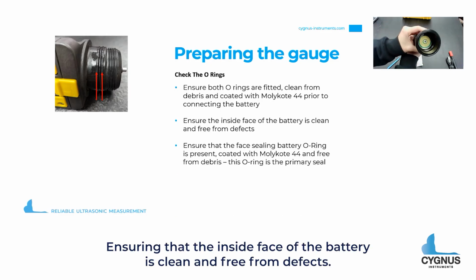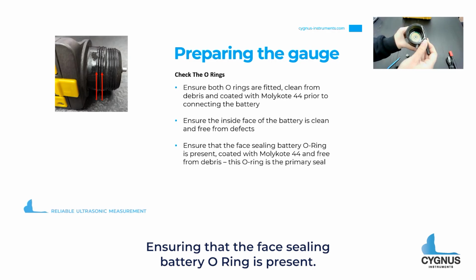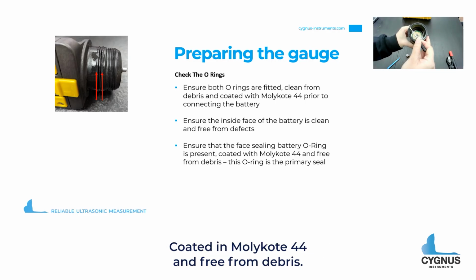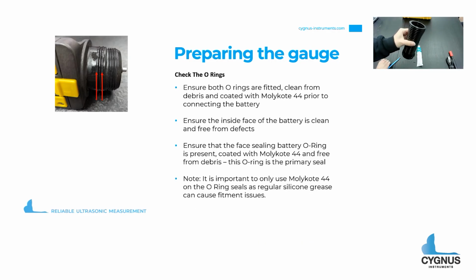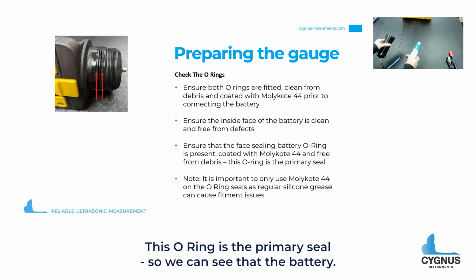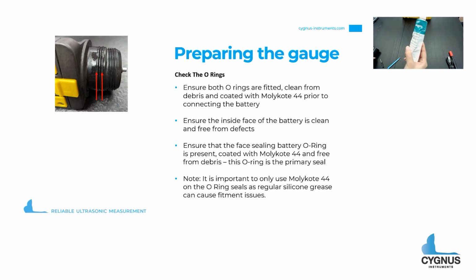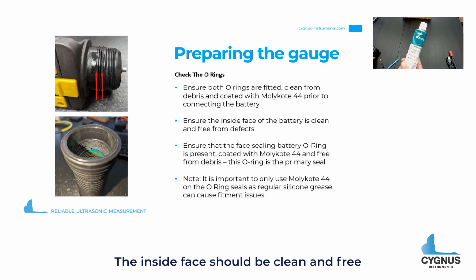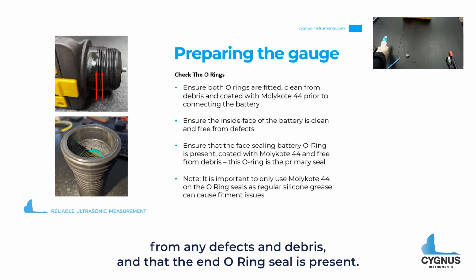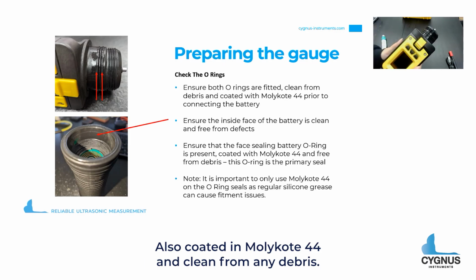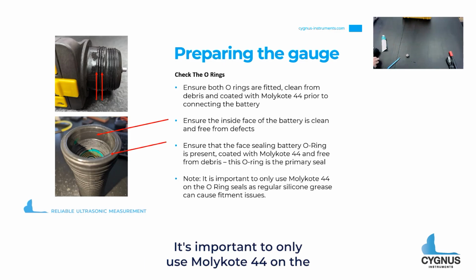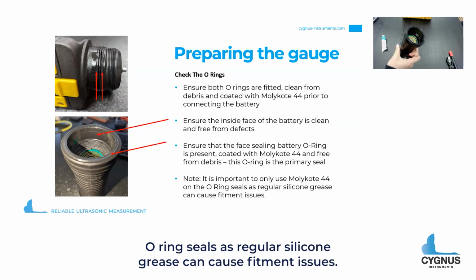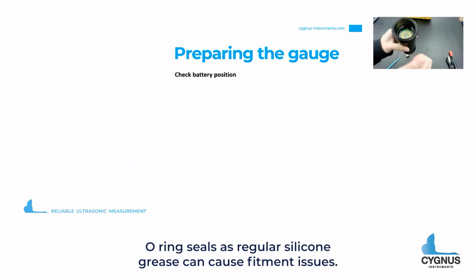Ensure that the inside face of the battery is clean and free from defects. Ensure that the face sealing battery O-ring is present, coated with Molykote 44 and free from debris. This O-ring is the primary seal. So we can see there the battery, the inside face should be clean and free from any defects and debris, and that end O-ring seal is present, also coated with Molykote 44 and clean from any debris. It's important to only use Molykote 44 on the O-ring seals, as regular silicone grease can cause fitment issues.